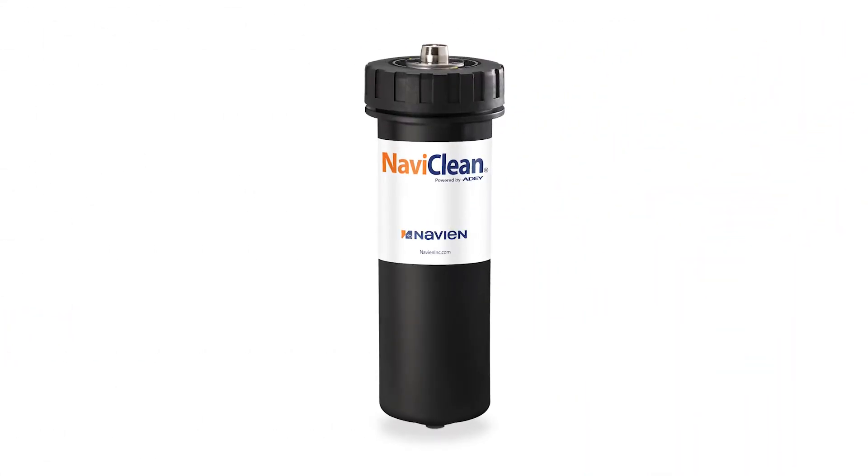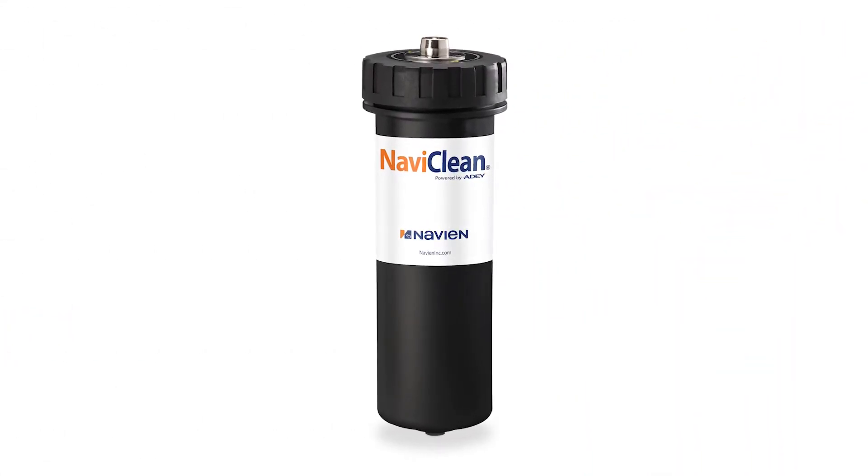With today's modern hot water boilers, like the Navien Combis or the Navien hot water only boilers, it's imperative to have good water quality. Water carrying any debris or sediment back to the boiler will shorten the longevity of not only the boiler but any components included in that system.